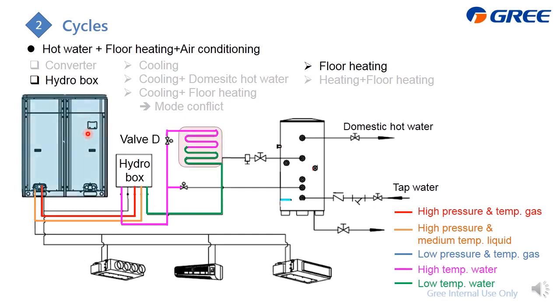So how about we add this indoor unit in heating? For example, if these two require heating, then we also send the hot gas from here to the indoor unit, and after it becomes liquid, it is collected and joined together with the liquid piping from the hydro box, then together goes back to the outdoor unit. Also in summary, this floor coil and the indoor units are doing heating and the outdoor unit is doing cooling.